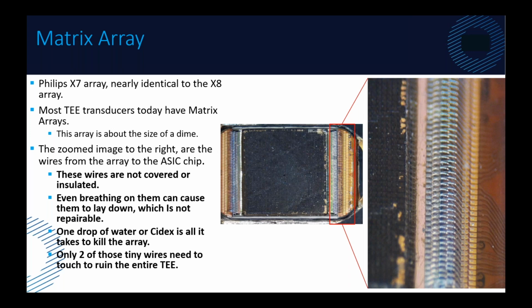So you can imagine what one drop of water does. One drop of water, or Cidex, or cleaner hits that, and that is a probe killer. Those probes don't come back, because nobody else can manufacture that array. We can fix a lot of things, but when the array's gone, that's one thing we can't fix. That's really what happens. The bad news is there's no water protection throughout the entire length of the insertion tube, which means you can introduce water on any part of this TEE probe, and it will get to the tip unless it dries out before it gets there. We'll talk about that as we move forward.